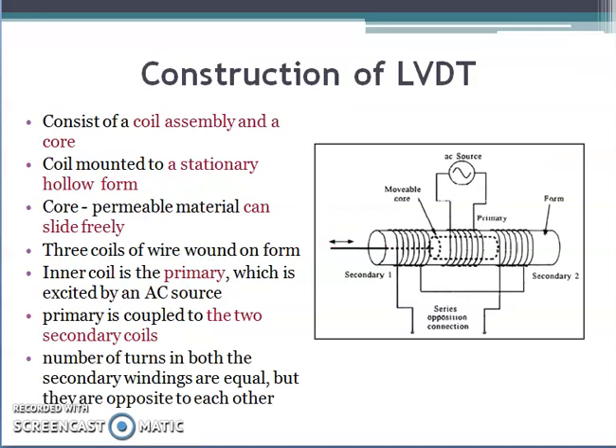Construction of LVDT. As shown in the figure, LVDT consists of a coil assembly and a core. The coil assembly is typically mounted to a stationary form, while the core is secured to an object whose position is being measured. The coil assembly consists of three wound wires on a hollow former. The core, made of a permeable material, can slide freely through the center of the former.